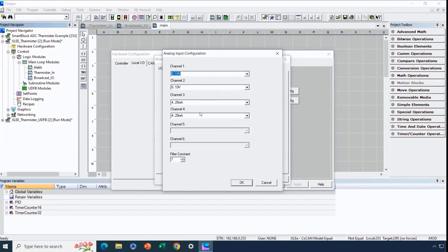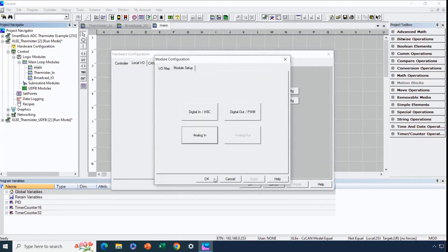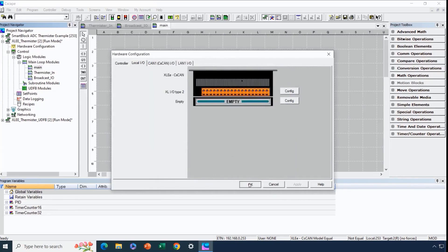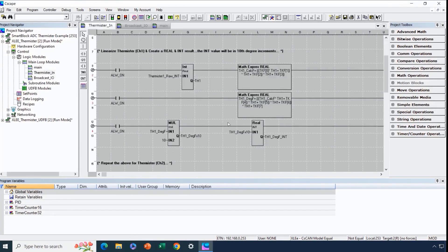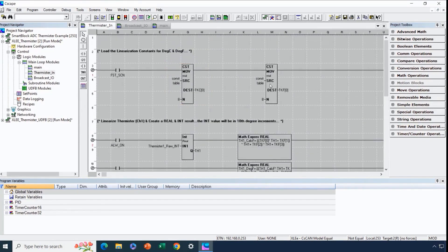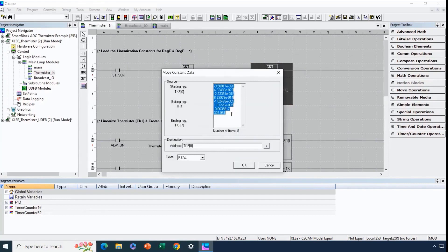Since this is a dash-10 two-channel module, we've opted for voltage for the first two channels, and for the second two channels we select whatever type of temperature sensor is used there. We've also put the filter constant up to 7, as that gives a really stable reading. That gets an analog input value coming from the built-in module into our analog input register, but it doesn't linearize or convert to temperature. That's where the equation comes in. We've moved eight coefficients provided in the thermistor supplement into a constant move block — they are in scientific notation with six-digit levels of precision — and we're copying these values into a real-type variable array with a dimension of eight.